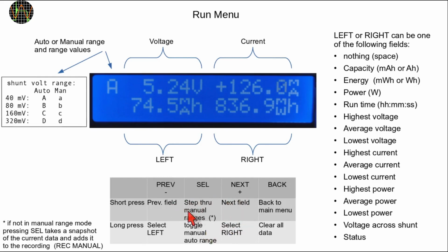You can see that I added the capability to change between auto and manual range directly from the run menu, because that's convenient when calibrating, for example, for a different shunt. There is an experimental manual recording mode which allows me to add a line with the current data to the recording file every time I press the select key in the run menu. Otherwise, no data is written to the file, even though recording is technically on. This is quite useful because it captures only the data I'm really interested in, instead of having to find it in the thousands of lines produced by regular recordings.